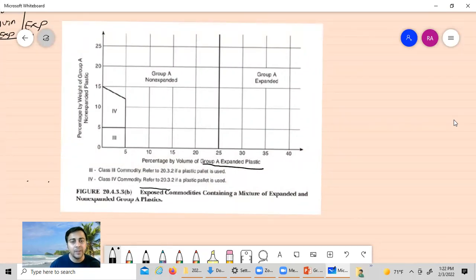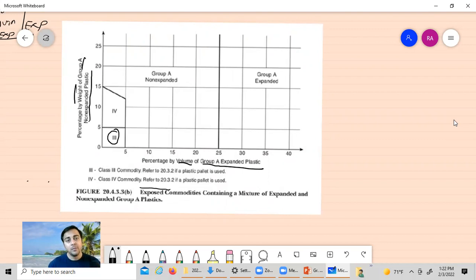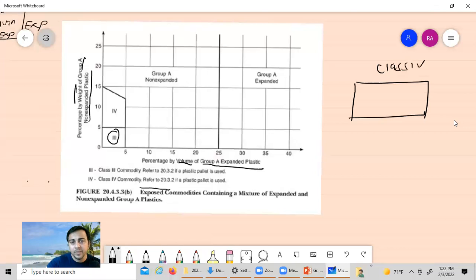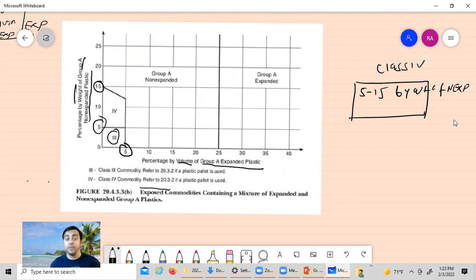Again, the x-axis shows Group A expanded plastic by volume and the y-axis shows Group A non-expanded plastic by weight. In Class III commodities you can keep 5% by volume or 5% by weight of Group A expanded or non-expanded plastic. For Class 4, you can keep 5% to 15% by weight of non-expanded plastic. However, for exposed commodities, anything greater than 5% expanded plastic is not considered Class 4 — it automatically becomes Group A non-expanded plastic.